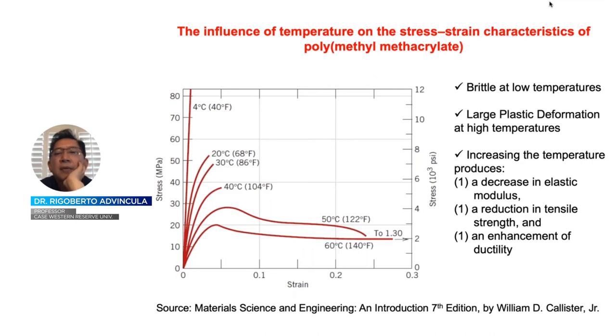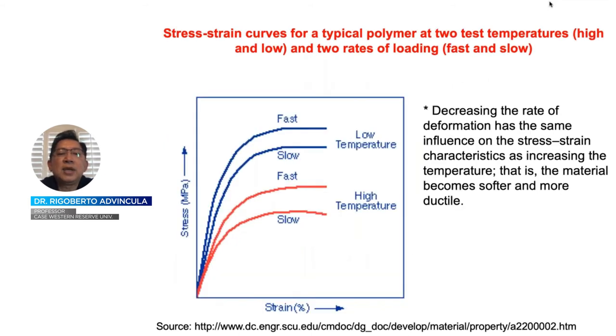There is a time-temperature correspondence of stress-strain characteristics. Most polymers, when heated or when the temperature of the environment increases, become more elastic or display larger plasticity compared to a low-temperature environment. This is common knowledge but also quantifiable using tensile measurement properties. The lesson is that when you report your testing protocol, you need to specify the temperature.